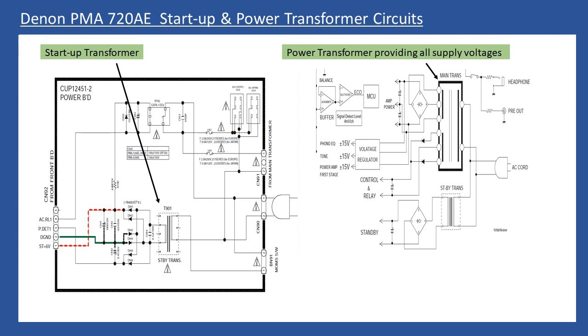How you identify the fault is: if you initialize the power, it tries to energize and you hear it click, but then you hear the startup relay de-energize, and the front LED just strobes and flashes red. That gives you a good indication that the primary is open circuit, which is unfortunate.